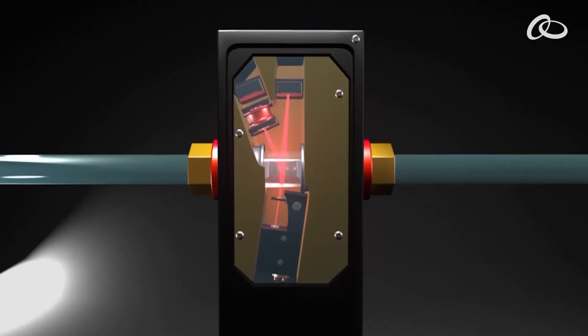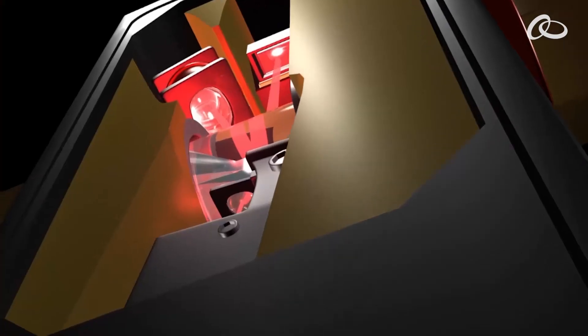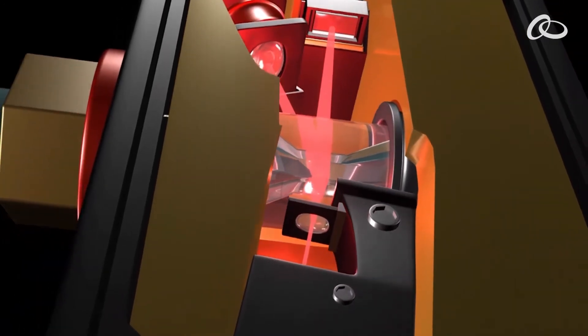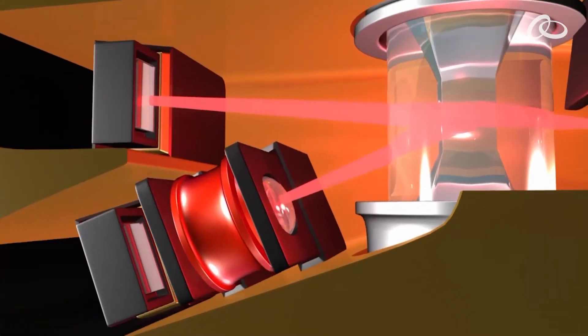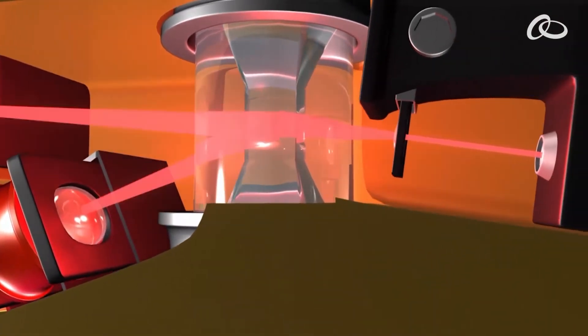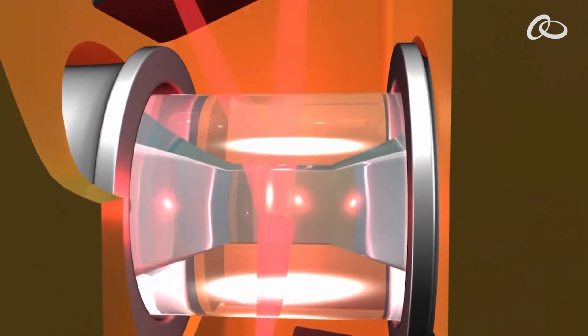As particles in a liquid suspension pass one at a time through a sensor, they both block and scatter the incident laser light. Both extinction and scattering detectors generate pulses proportional to the size of the particle. A pulse height analyzer converts these pulses into a particle size through the use of a calibration curve.